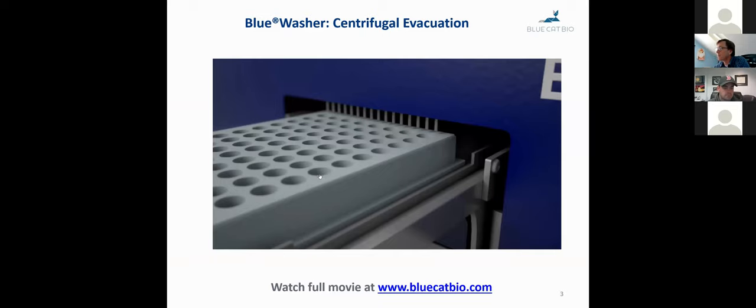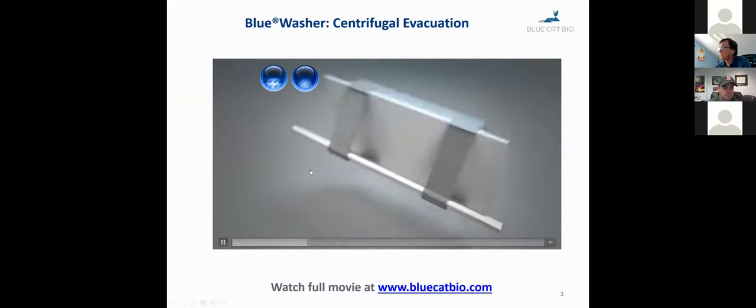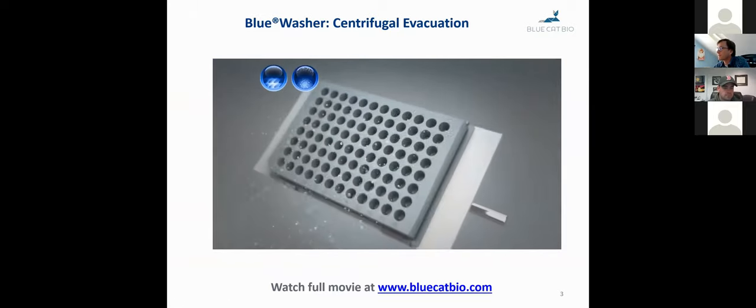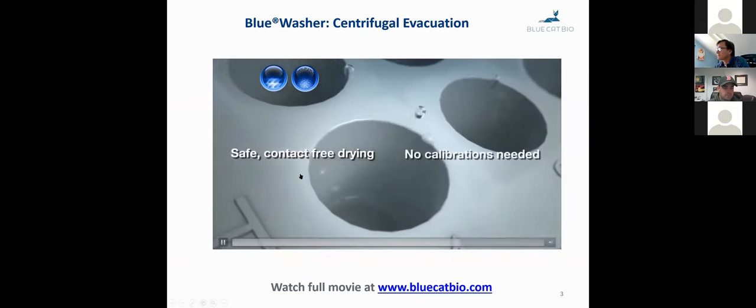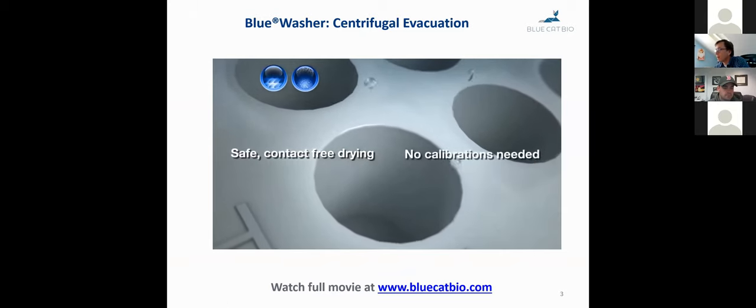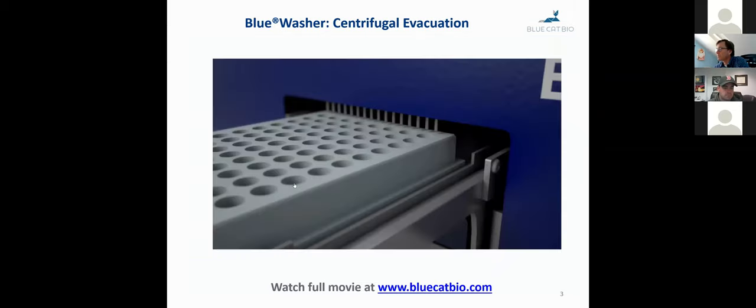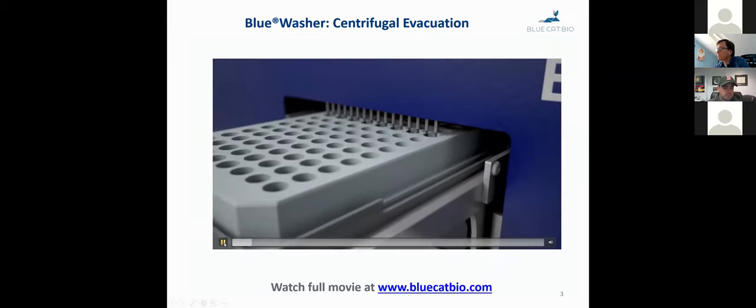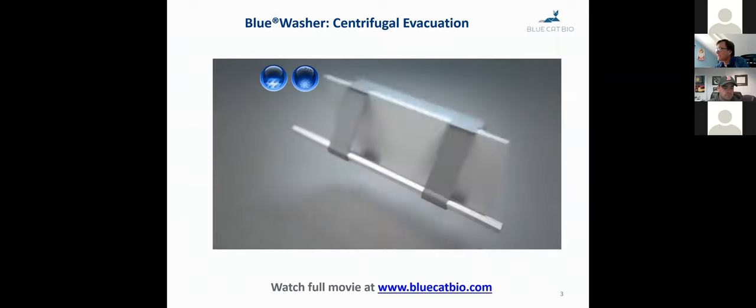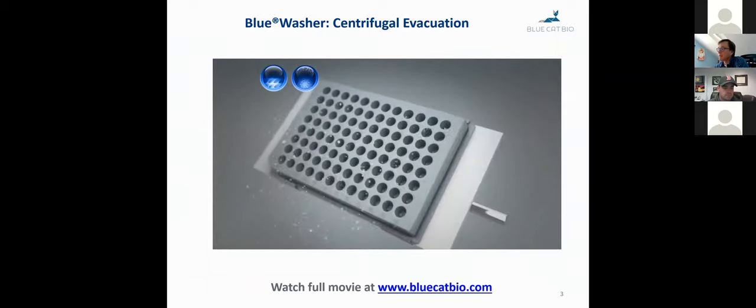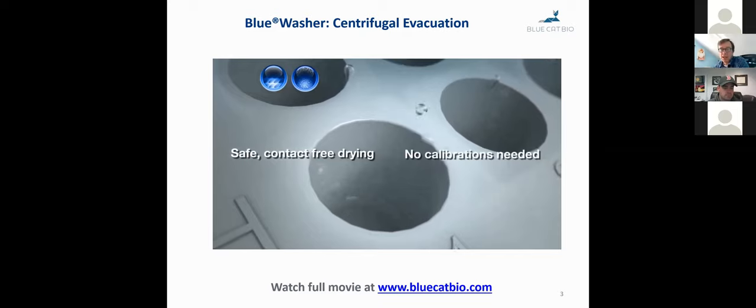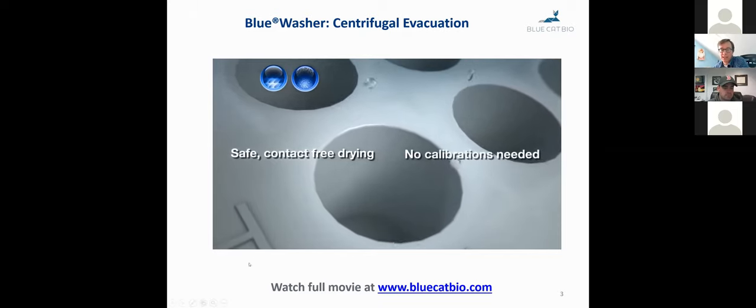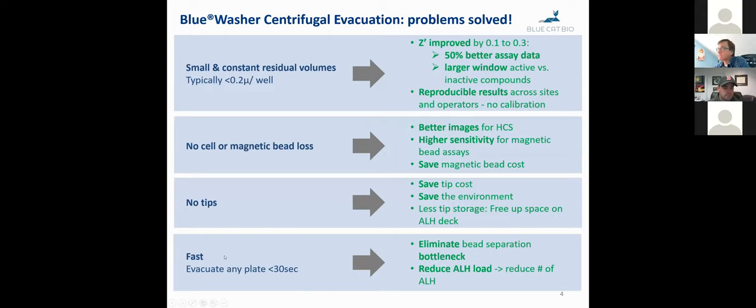So the solution that we have is centrifugal evacuation with a blue washer. I just want to show you this quick movie. So that shows the principle of centrifugal evacuation. I'm just going to run it again. So the blue washer dispenses liquids into the plate, and then inside, the plate spins around a horizontal axis, and the centrifugal force then basically safely pulls the liquid out of the wells with no contamination. And that solves the problem.